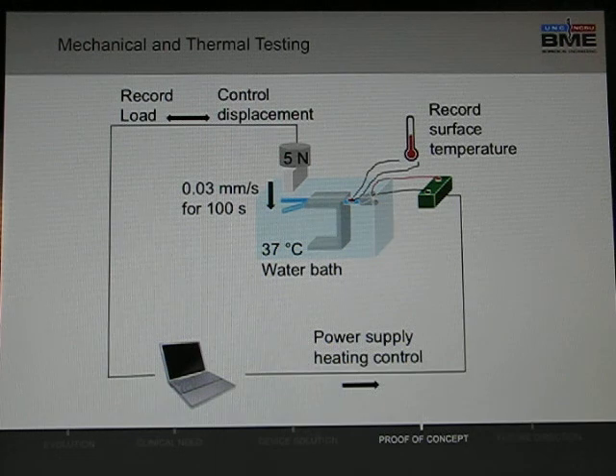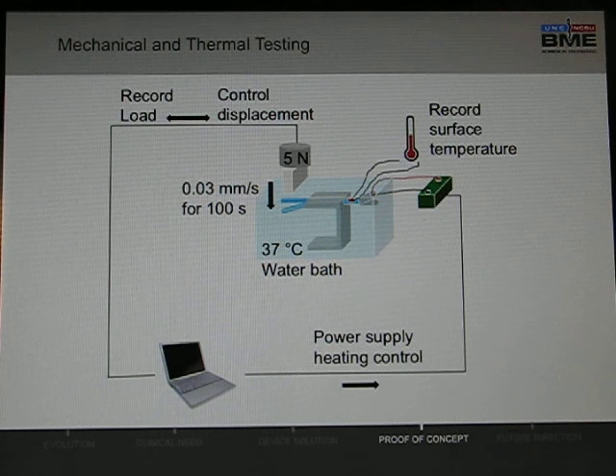So we went forward and did some mechanical and thermal validation studies. Here we have schematically shown our experimental setup. We have the power supply in green, which is controlled by the computer, and the power supply is connected to the catheter and activates the catheter. We record the surface temperatures. We applied cantilever bending similar to the tubes by controlling displacement, and we record the loads.